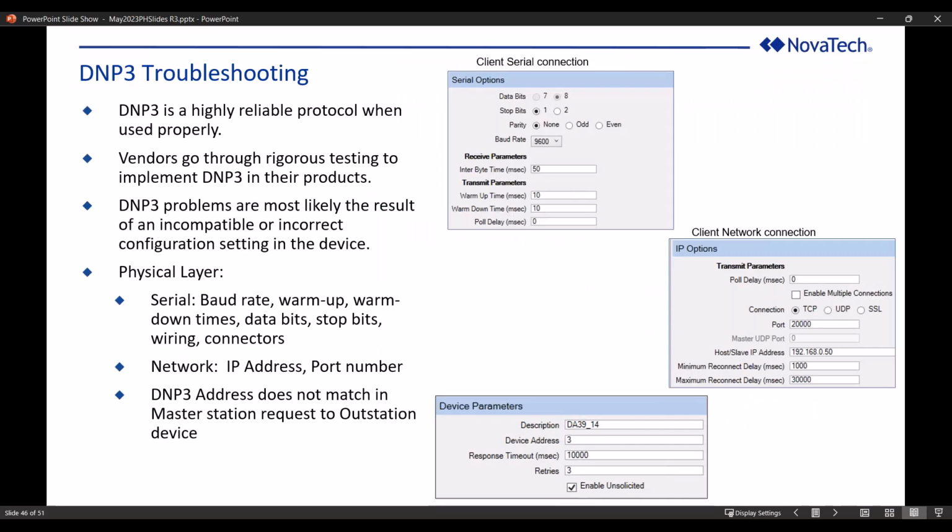All right, so some troubleshooting tips, based on my experience with DNP3. We're always aware that server and client always need to match up, right? So for troubleshooting, number one, we always want to make sure the DNP3 address configured on your server and client matches up. There's always a server address that's configured on both sides, and the client address. Depending on the application, you might not need to configure on the server side what client I'm reporting to, but you just need to double check your addresses.